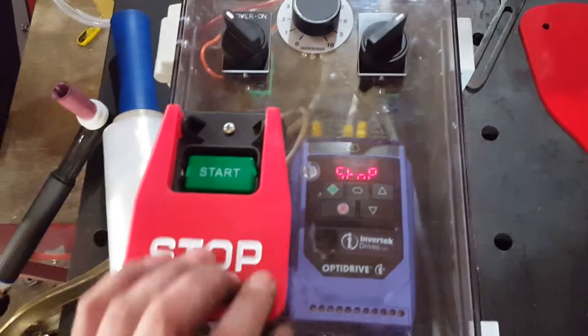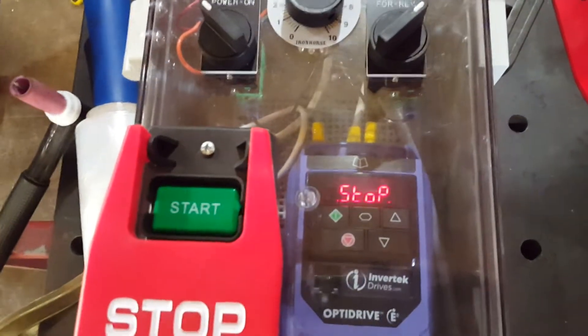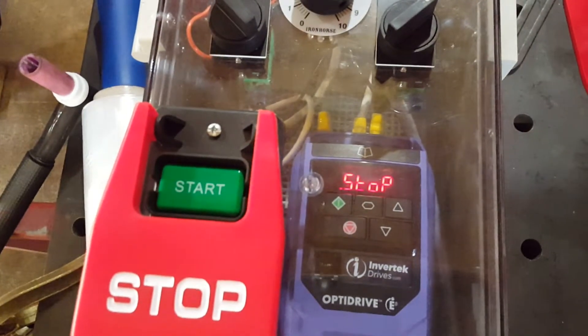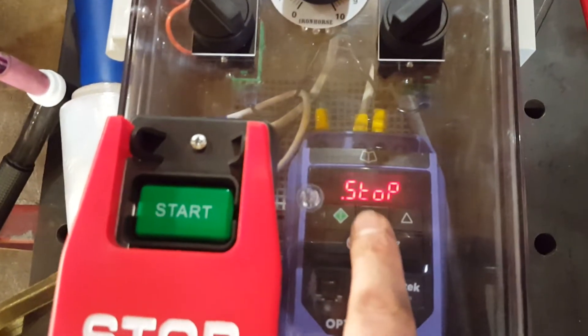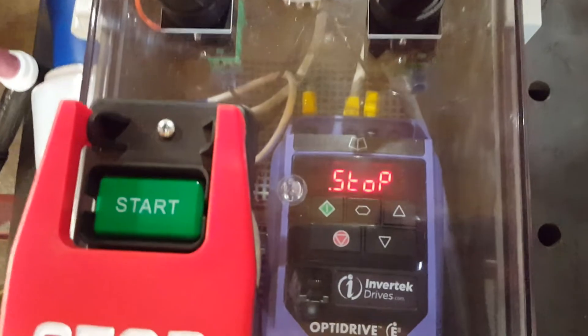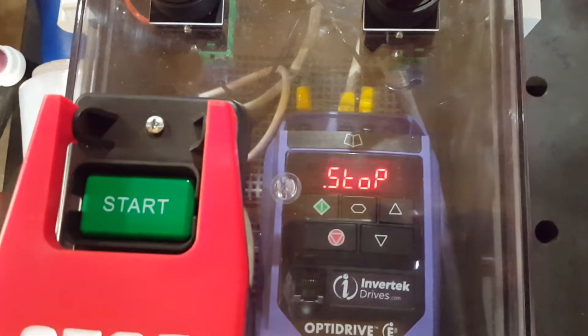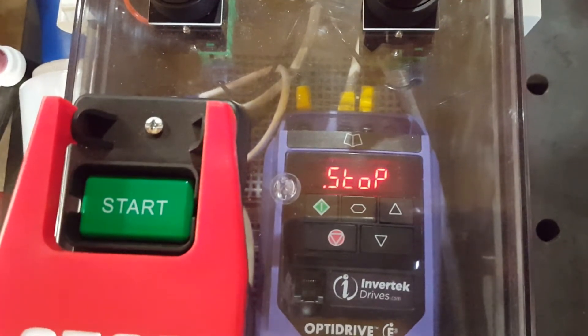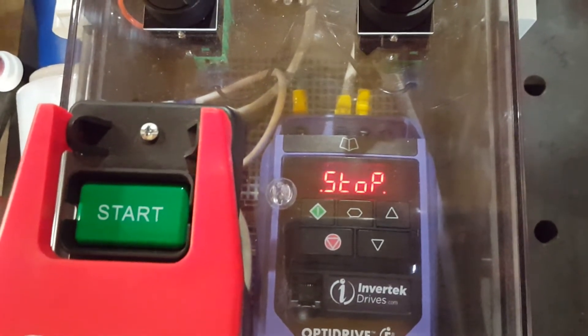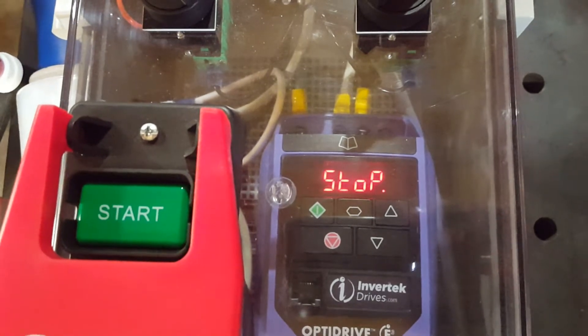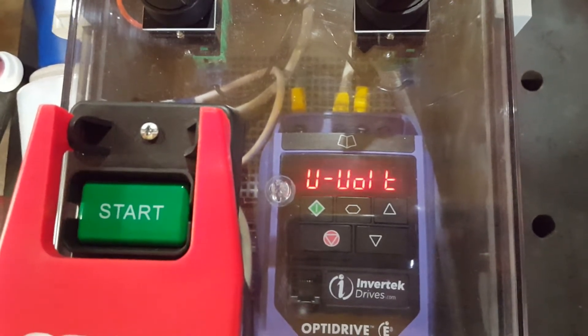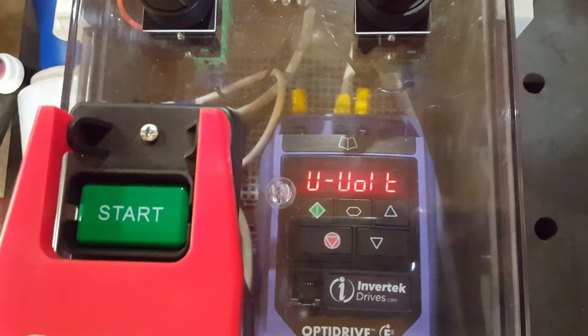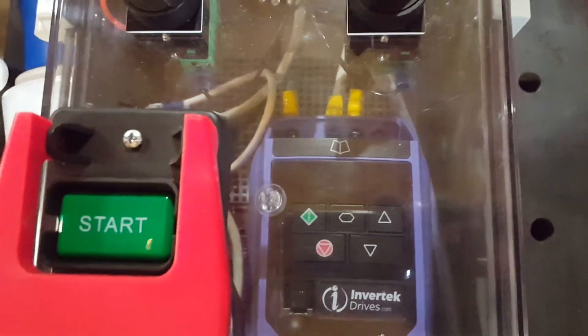If you hit this big stop button here, at this point the plug is not hot, but you can see the capacitors are discharging. So until that display turns off, you can still get a jolt. I've shocked myself. It's not going to kill you, but under voltage, now it's off.